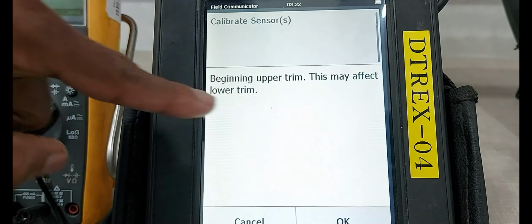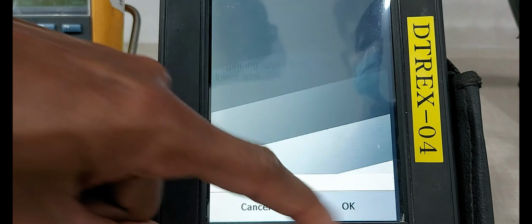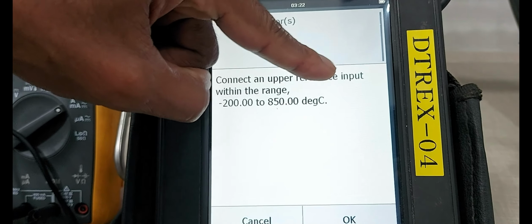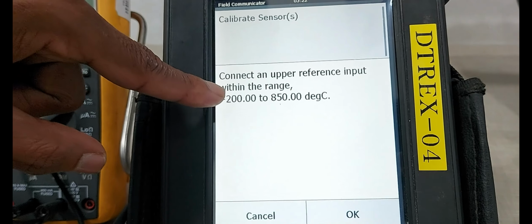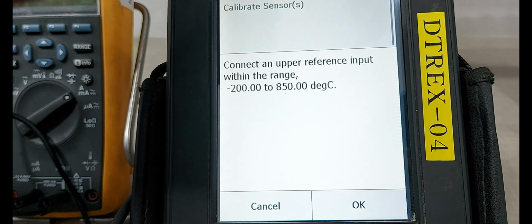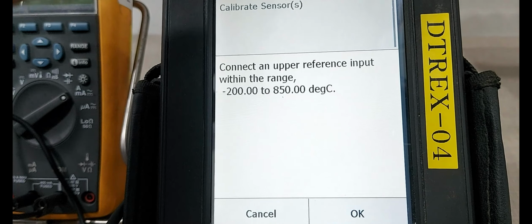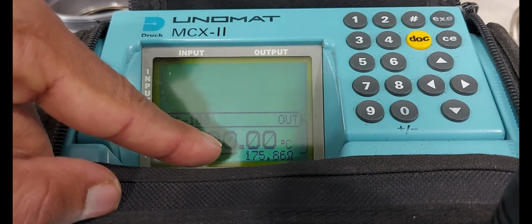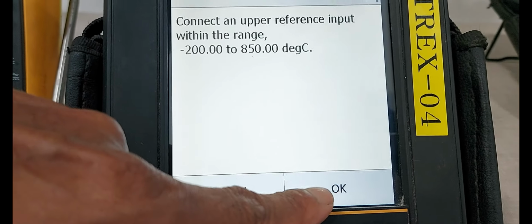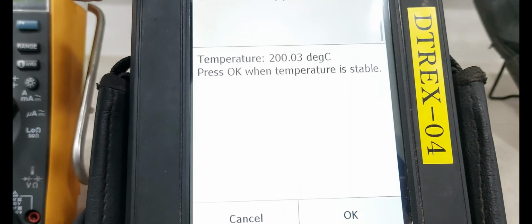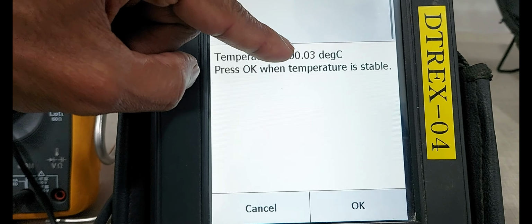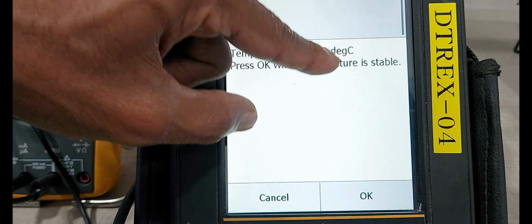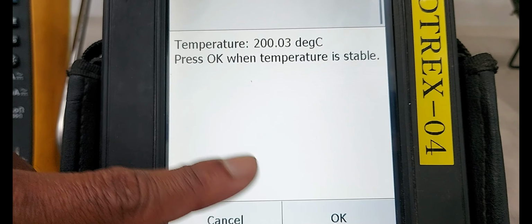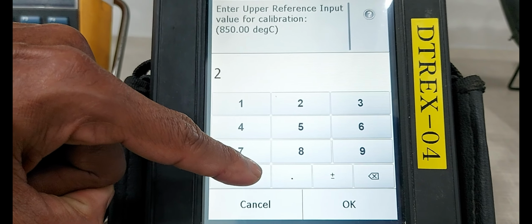Beginning the upper trim, this may affect the lower trim, OK. Connect the upper reference input within the range -200 to 850 degrees. Our calibration range upper value is 200 degree. 200 degree already applied. Press OK. Okay, temperature showing 200.03 degree. Press OK when temperature is stable. Now temperature is stable. Okay. Enter the upper value, 200 degrees upper value.